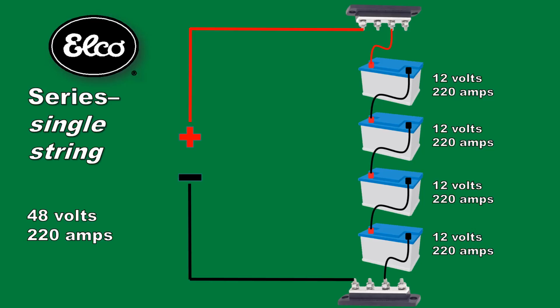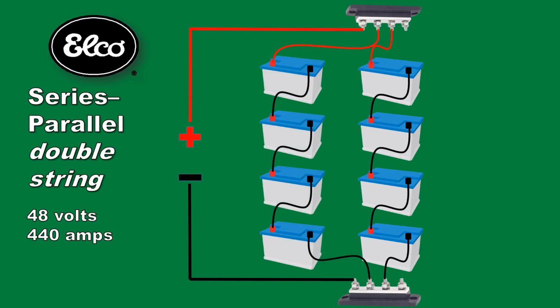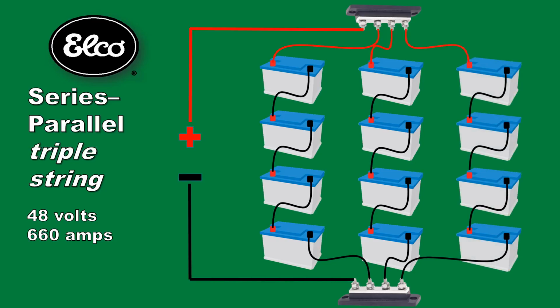This does not increase the amp-hour rating of the string, which remains the same. If your runtime requirements exceed the amp-hour rating of your single 4-battery string, you can add a second string, which would be connected to the first string in parallel. This is called a series parallel configuration. A parallel string of batteries doubles the battery amp-hour rating, but keeps the voltage the same. A third string connected in parallel triples the amp-hour rating, and so on.